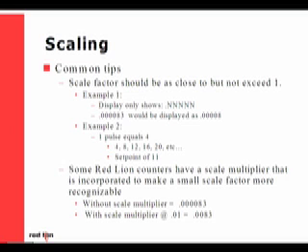Second, some Red Lion counters have a scale multiplier that is incorporated to make a small scale factor more recognizable. In our example, our scale factor without any multiplier is 0.000083. With a scale multiplier of 0.01 added, our scale factor now becomes 0.0083.